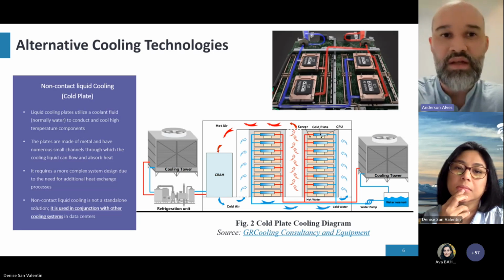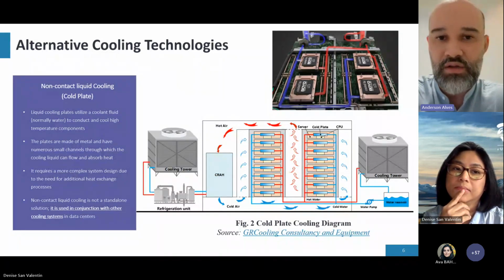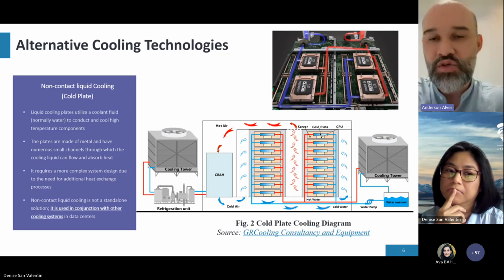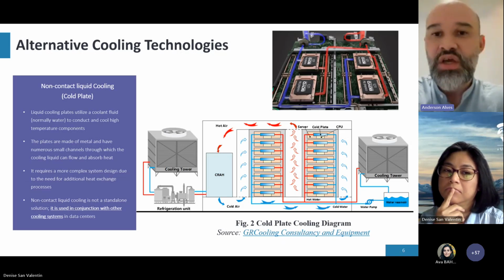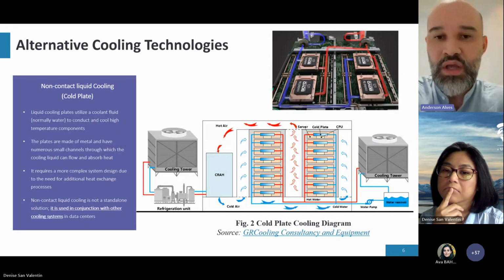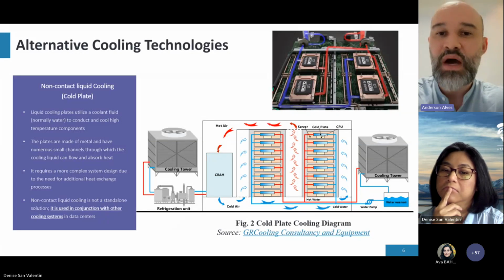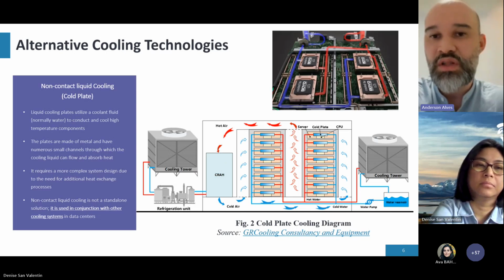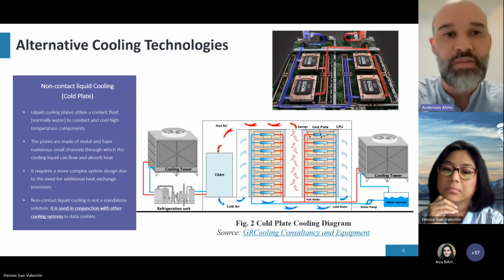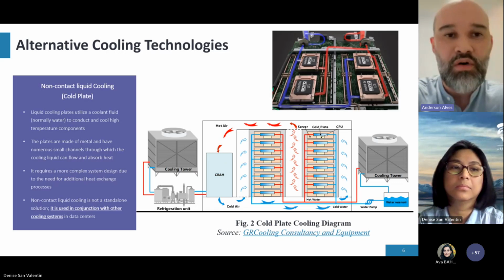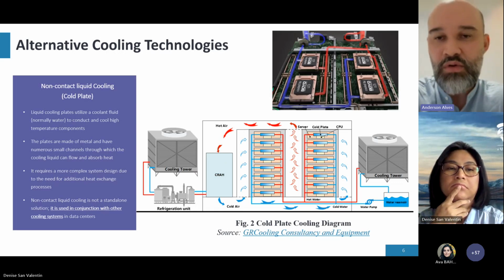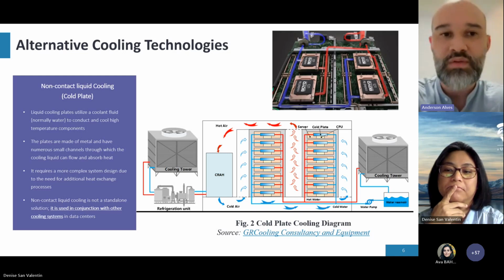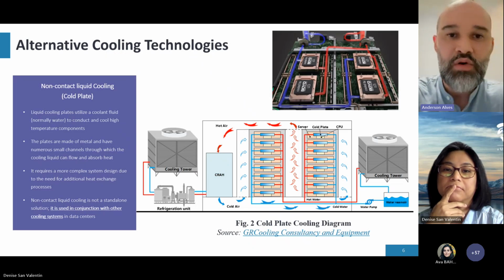Let me go back a bit - these are called liquid cooling technologies, where instead of air-to-air heat exchange, a determined cooling liquid is used in the middle to improve heat transfer. By improving heat transfer, you also improve energy efficiency, because in theory this technology consumes less energy. The first one we looked at was non-contact liquid cooling, meaning the liquid doesn't enter direct contact with the rack, CPUs, or GPUs. This first technology is called cold plate.